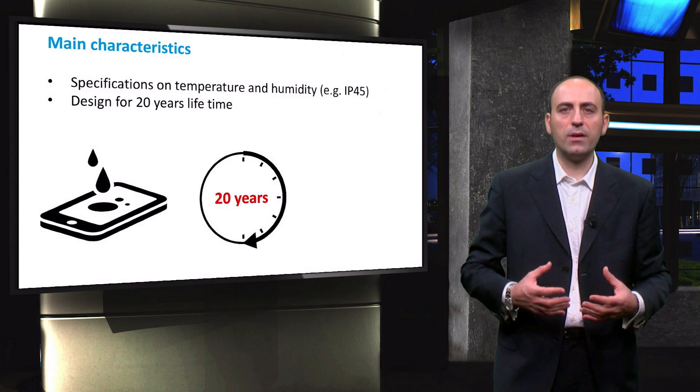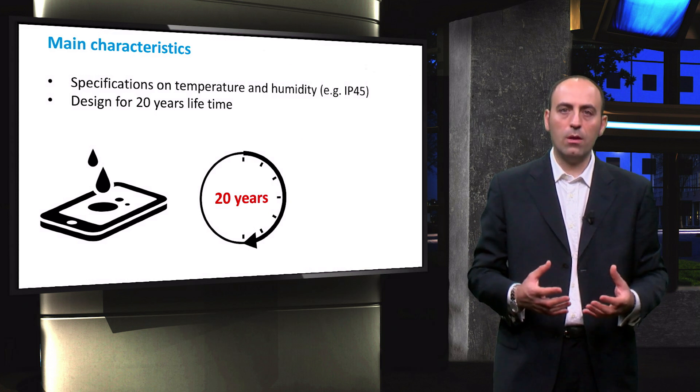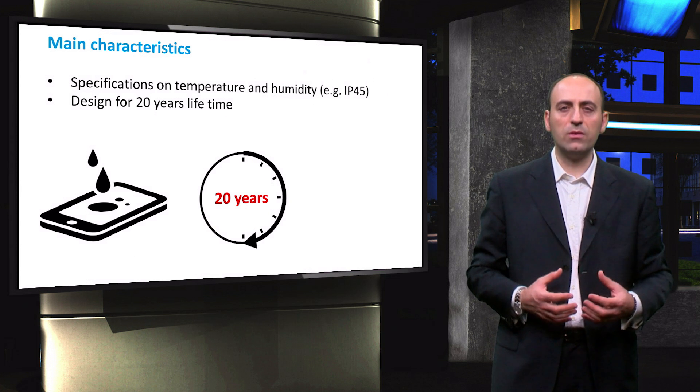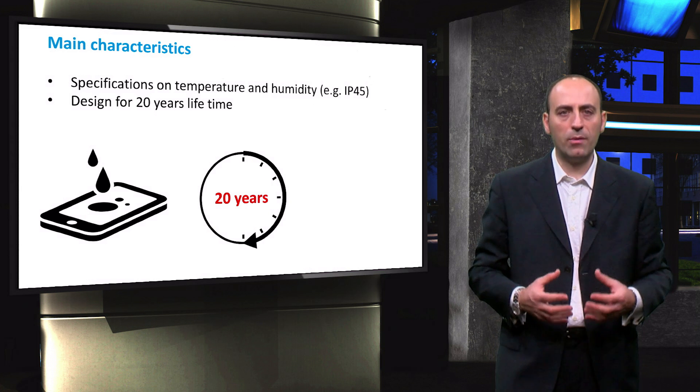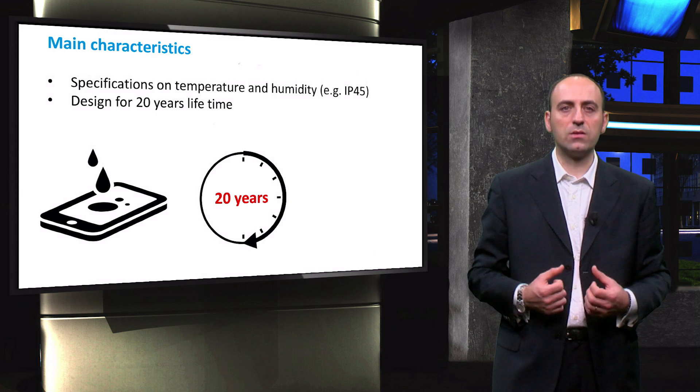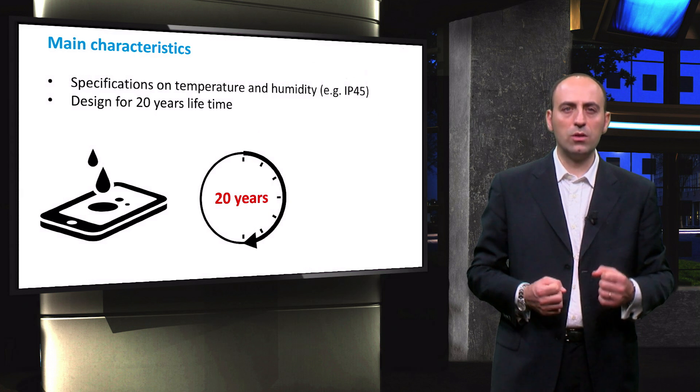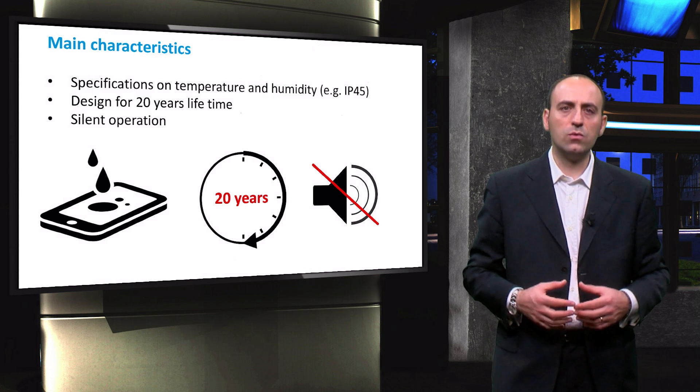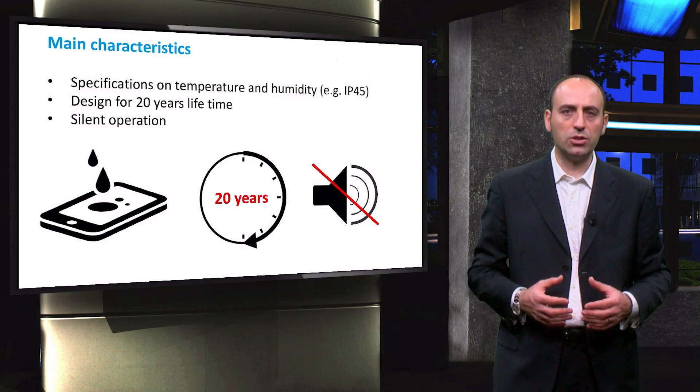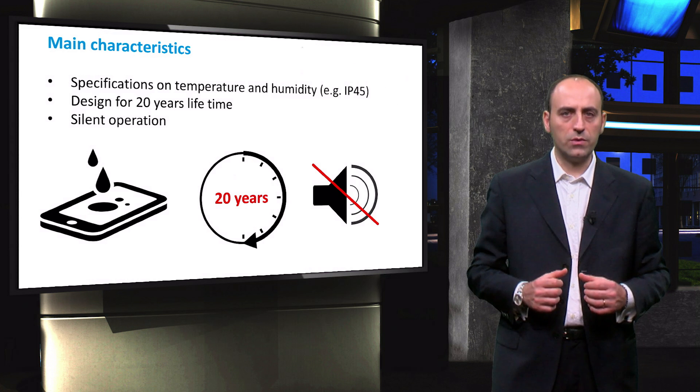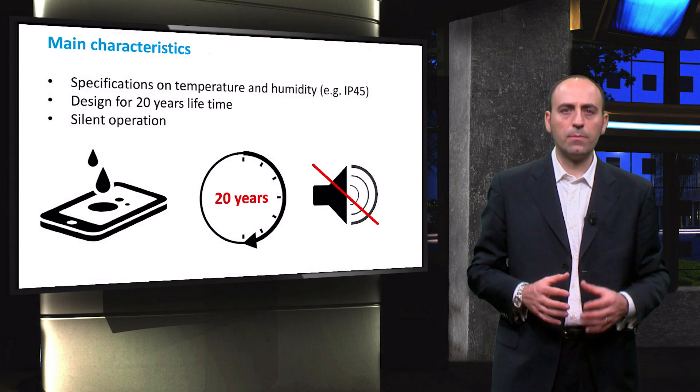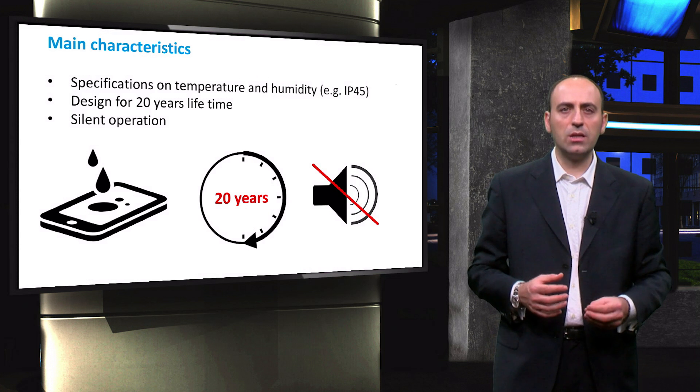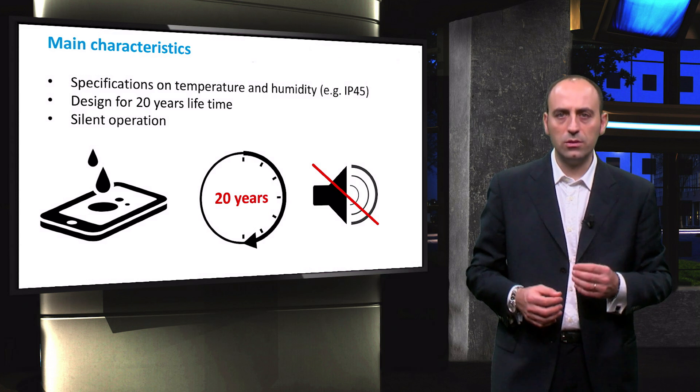Nowadays, these components are becoming more and more reliable, but power electronics and batteries still remain the most fragile part when it comes to maintenance, while PV panels are usually the sturdiest part of the PV system. Last aspect to take into account is the silent operation, so no audible noise. Often for inverters, when a loud clicking noise can be heard, it might be a signal of malfunctioning of the chopping section.